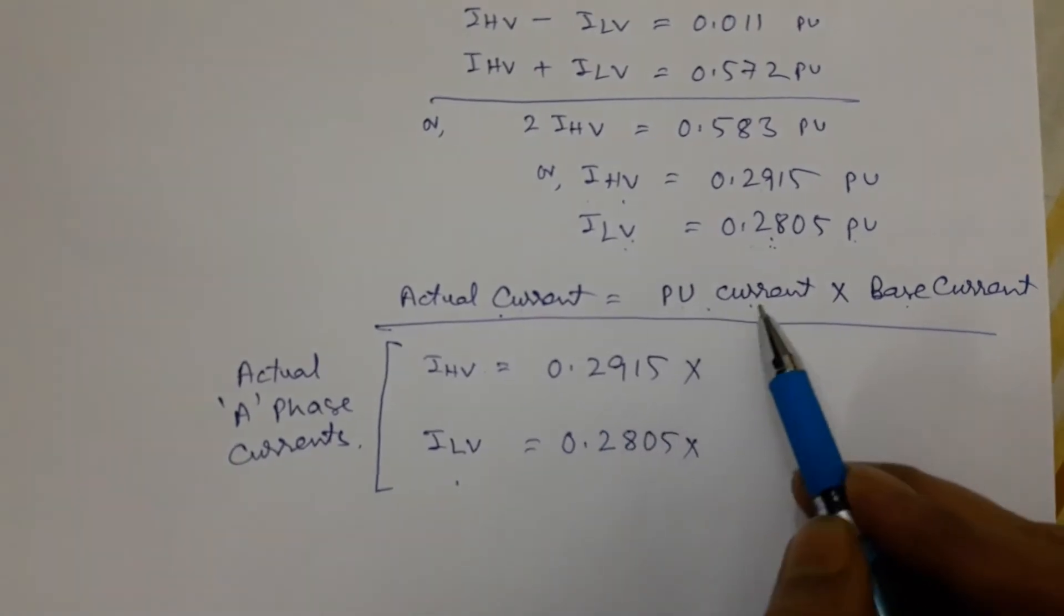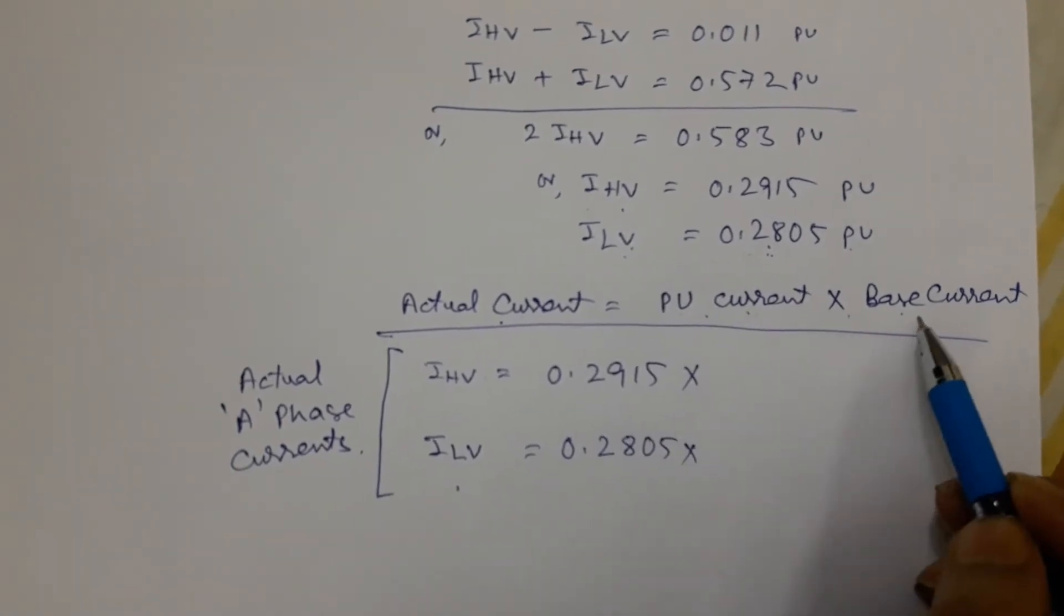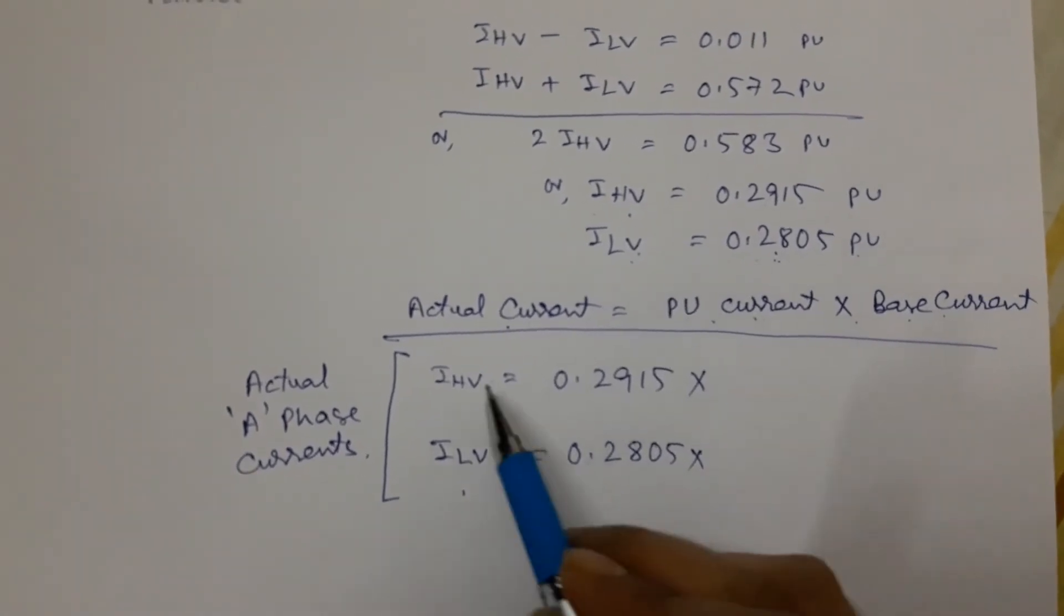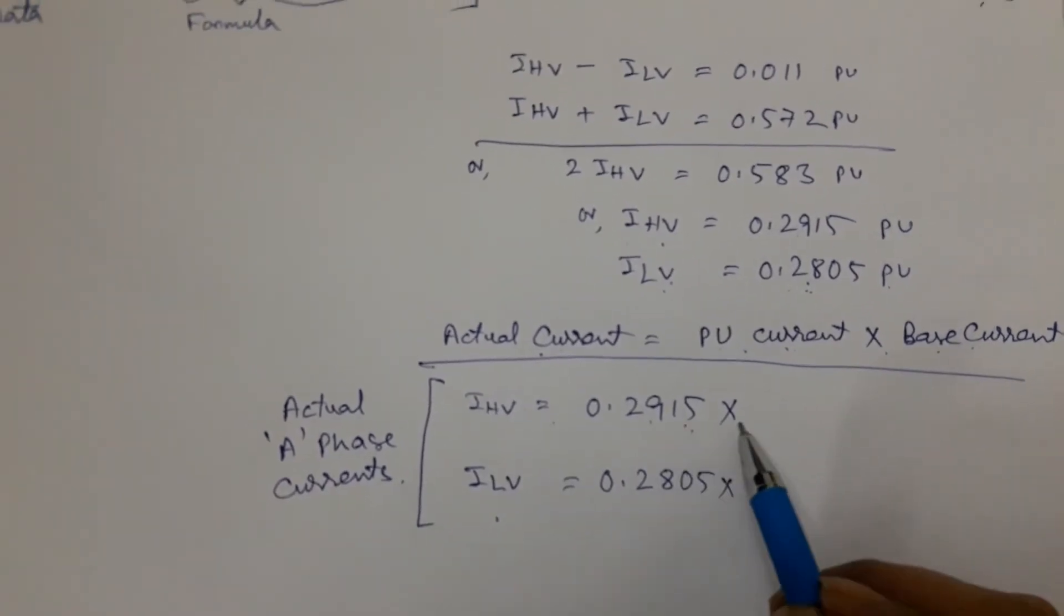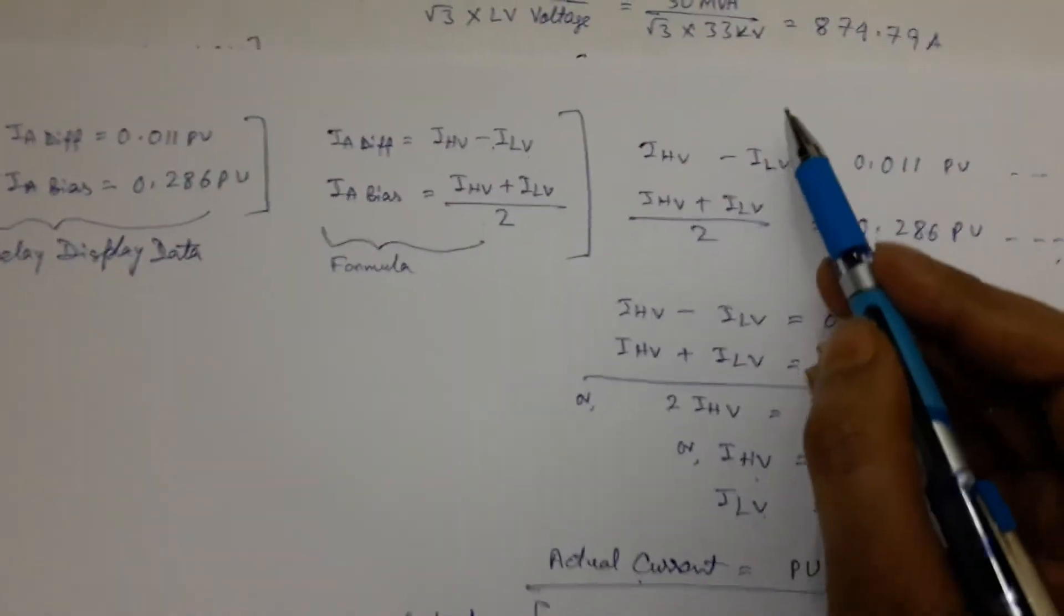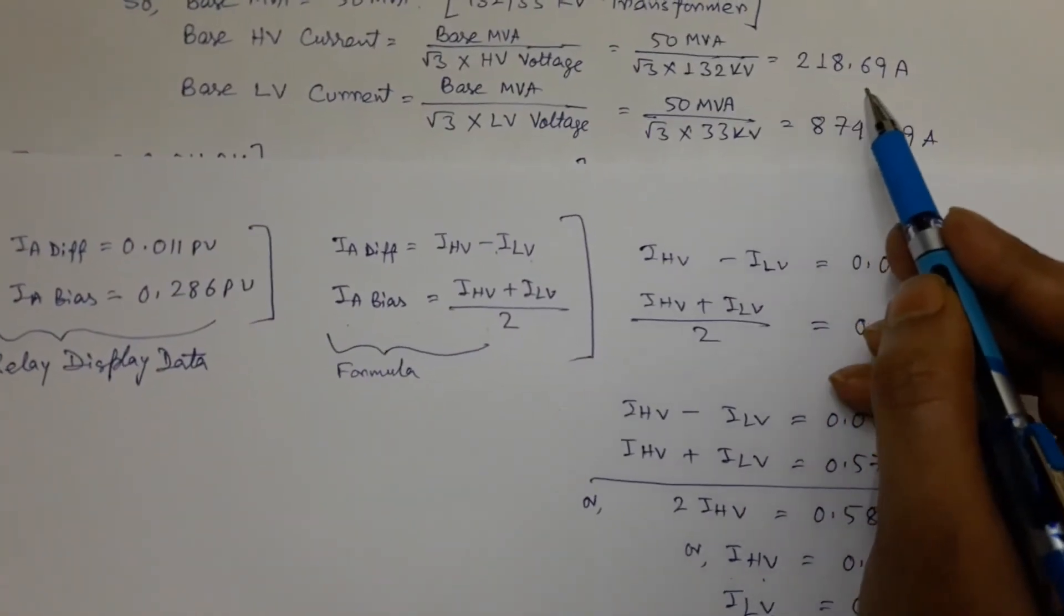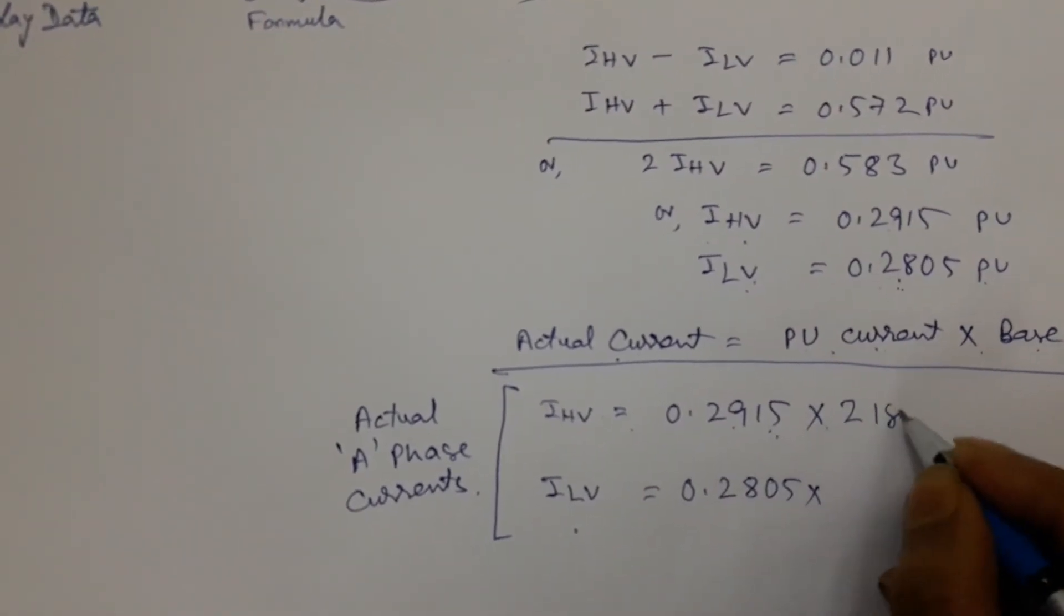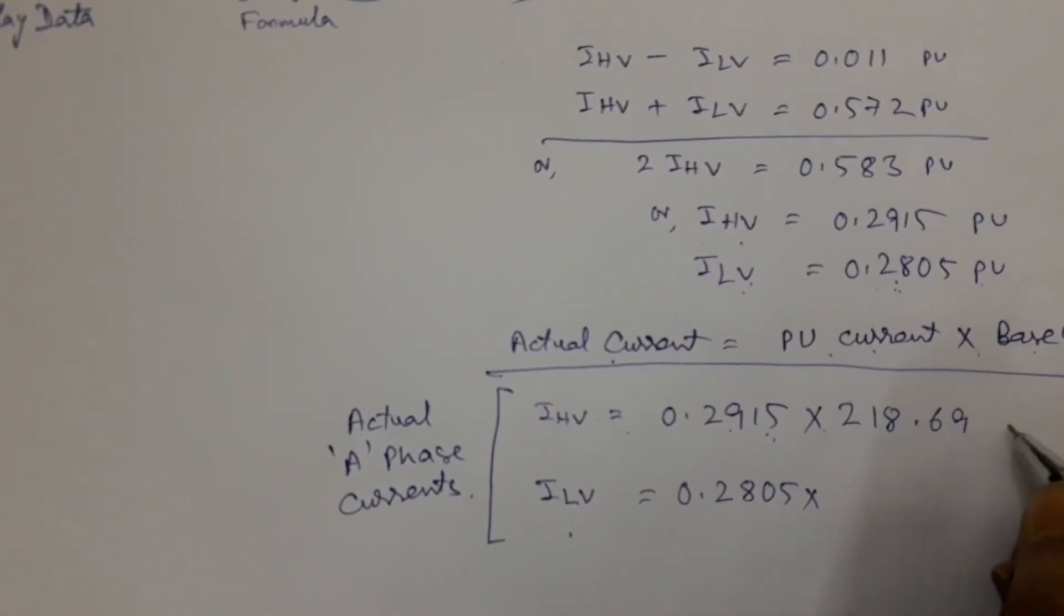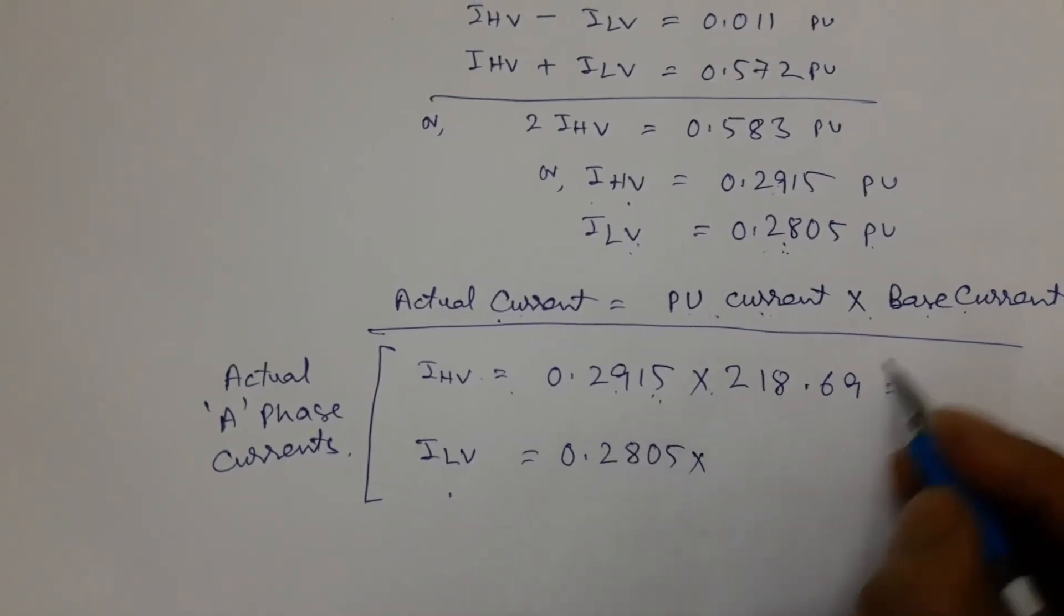Now for HV side per unit current, we already calculated. Base current, that is also we calculated before, that is 218 ampere, so 218.69 ampere. So by multiplying these two, we get the HV side current.